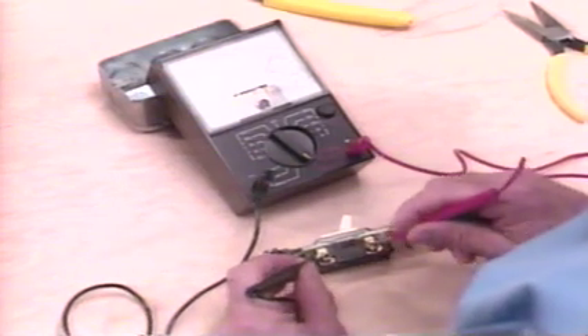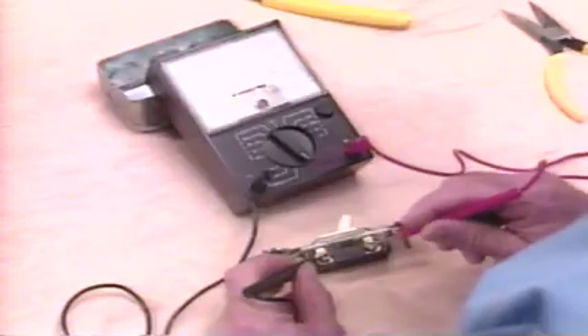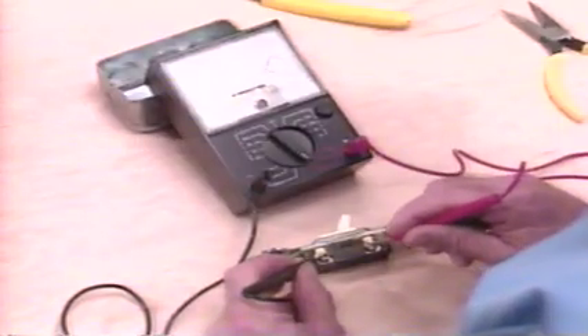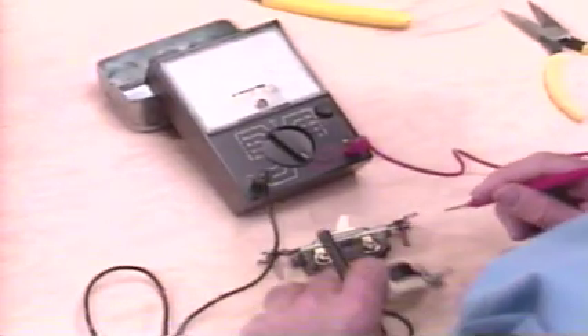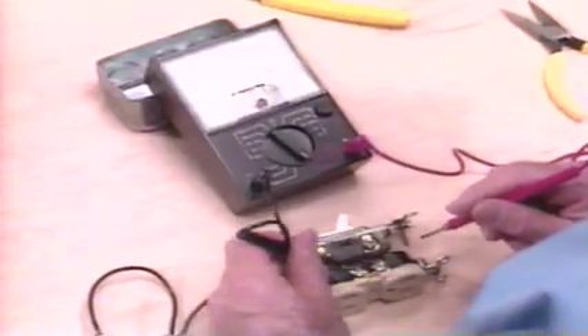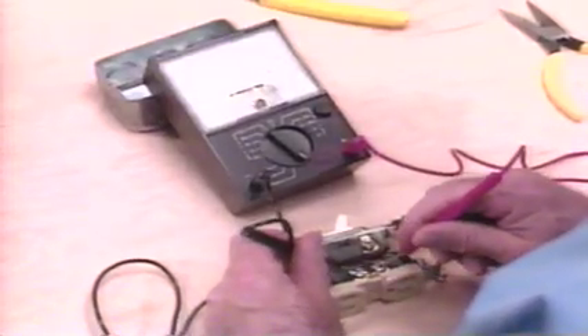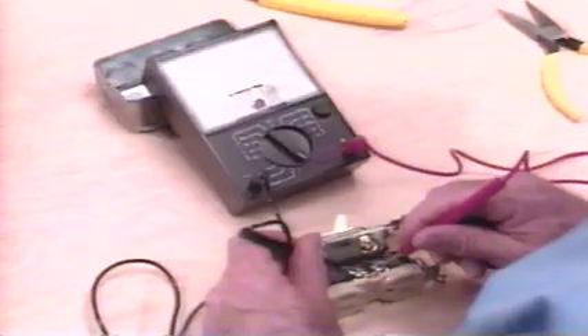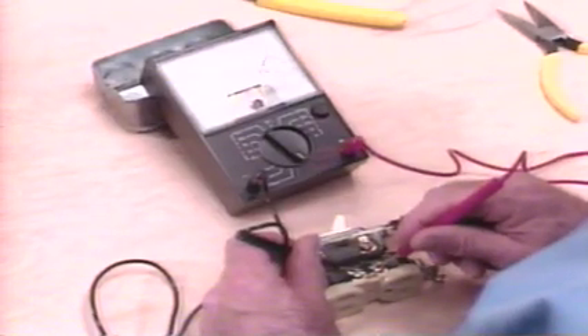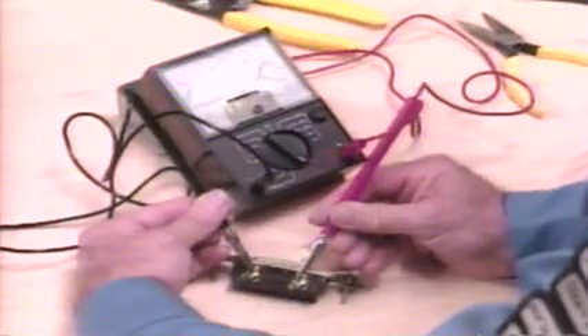to the electrical terminals of the part that's being tested, like these terminals of this switch or these terminals of this receptacle. Then note the reading. It is essential that the probes make good contact with the terminals being tested. If it's possible to use alligator clips on the terminals being tested, use them. These clips usually make a firmer connection than the probes.